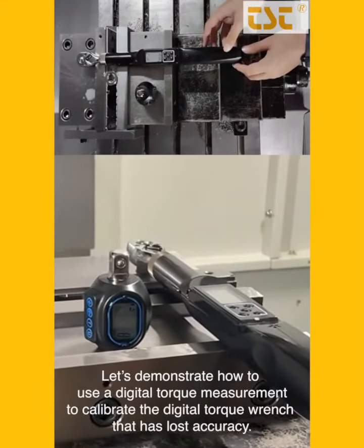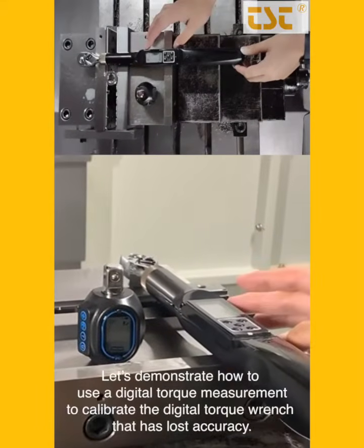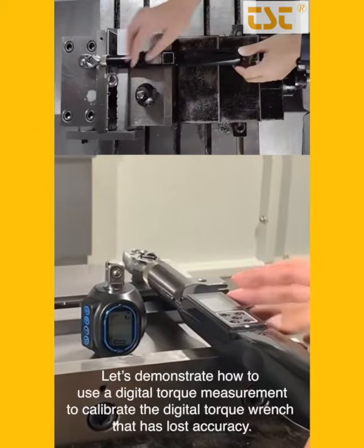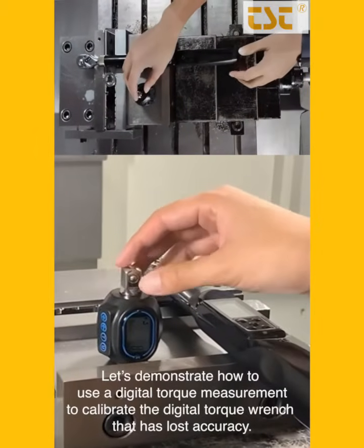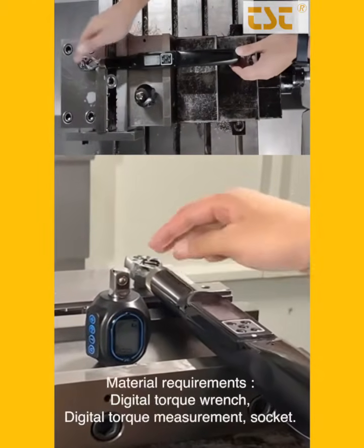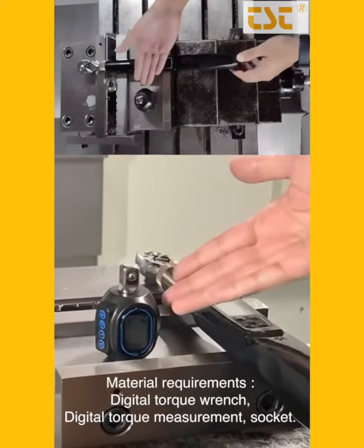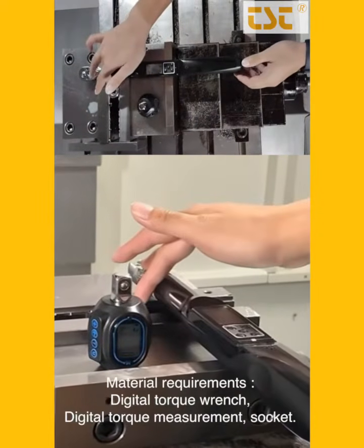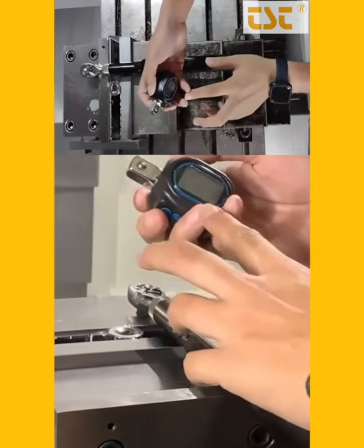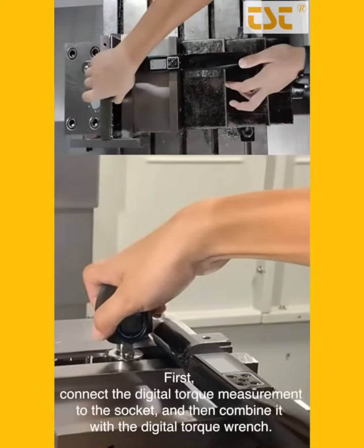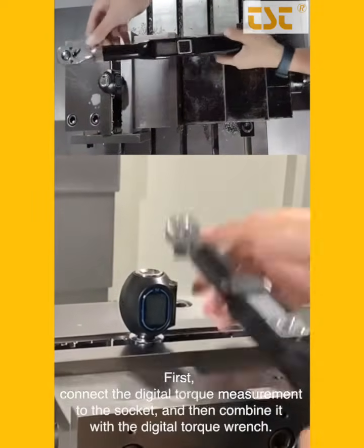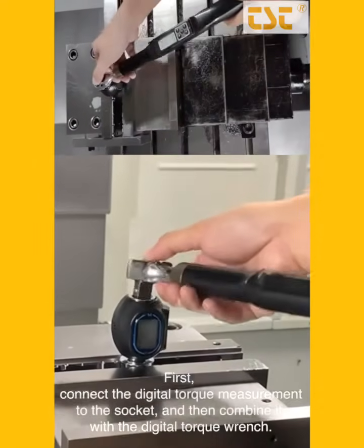Let's demonstrate how to use a digital torque measurement to calibrate the digital torque wrench that has lost accuracy. Material requirements: digital torque wrench, digital torque measurement, socket. First, connect the digital torque measurement to the socket, and then combine it with the digital torque wrench.